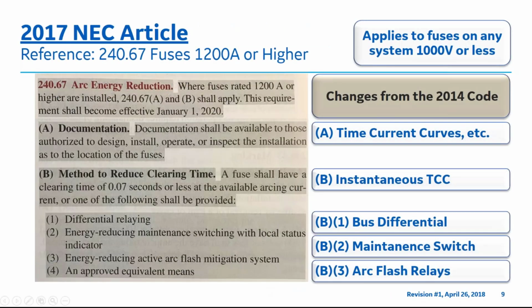The NEC is taking additional steps to solve the arc flash problem for fuses and increase safety for several types of facilities. In GE's collaboration with consulting engineers, end users, and EasyPower will hopefully reach a broad network. In general, electronic devices for fuses on any system 1000 volts or less are being introduced to help reduce arc energy for fuses per the following means.